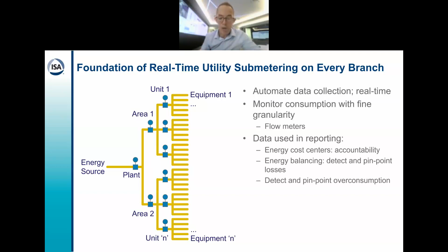Now, various types of flow meters are required. Water typically using mag flow, compressed air using DP flow, fuel or other gases using DP or Coriolis mass flow meters, electricity, well, that is provided from the motor control center and electrical switchgear. But steam, yes, using vortex or DP flow transmitters.